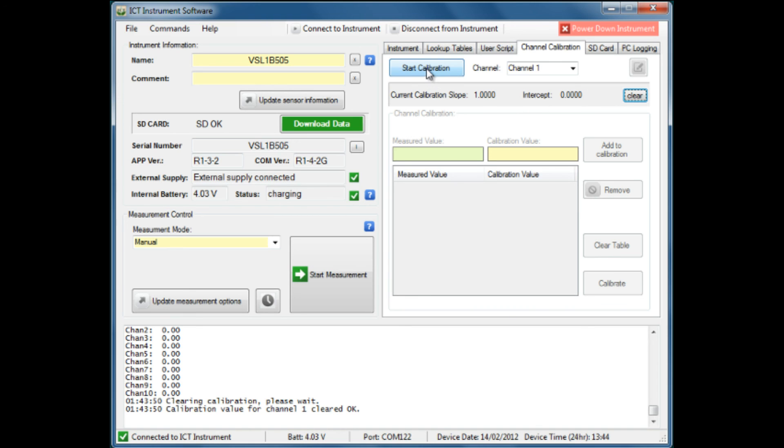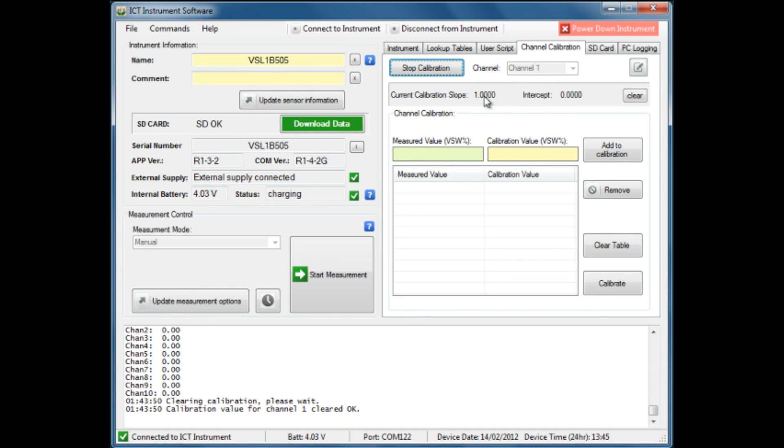We first of all have to start the calibration process. We're on channel 1, and the calibration slope is a factor of 1, which means there is no variation, so we are starting with a fresh calibration.